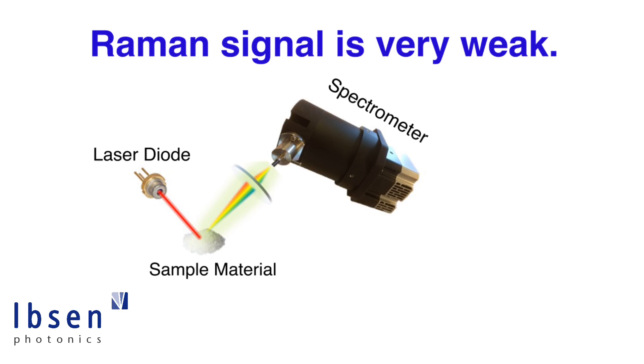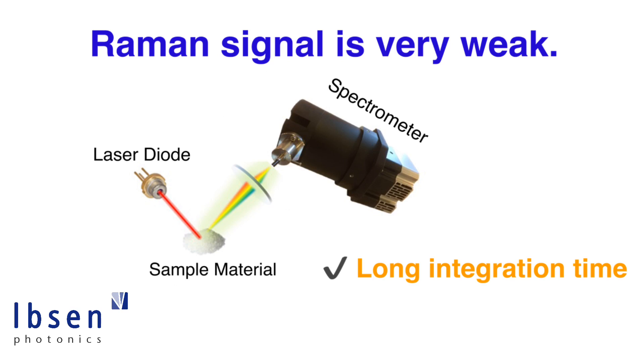For this reason, in Raman you use really long integration time. The integration time helps to collect photons as they come — you generate a charge in the detector every time there's a photon, so you wait for a long time and build up a strong signal. The downside is that when you build a strong signal, you also build a lot of noise or dark current electrons. To avoid that, you cool the spectrometers. So at least for high-end Raman, you always use long integration time and cooled detectors.